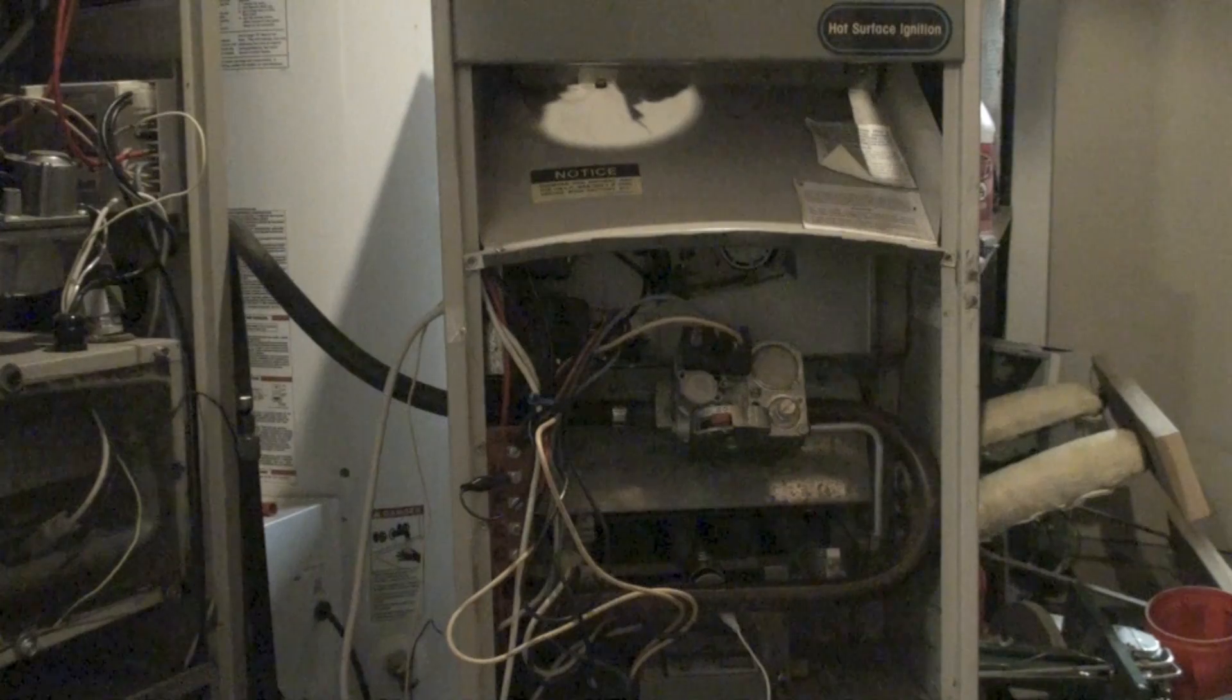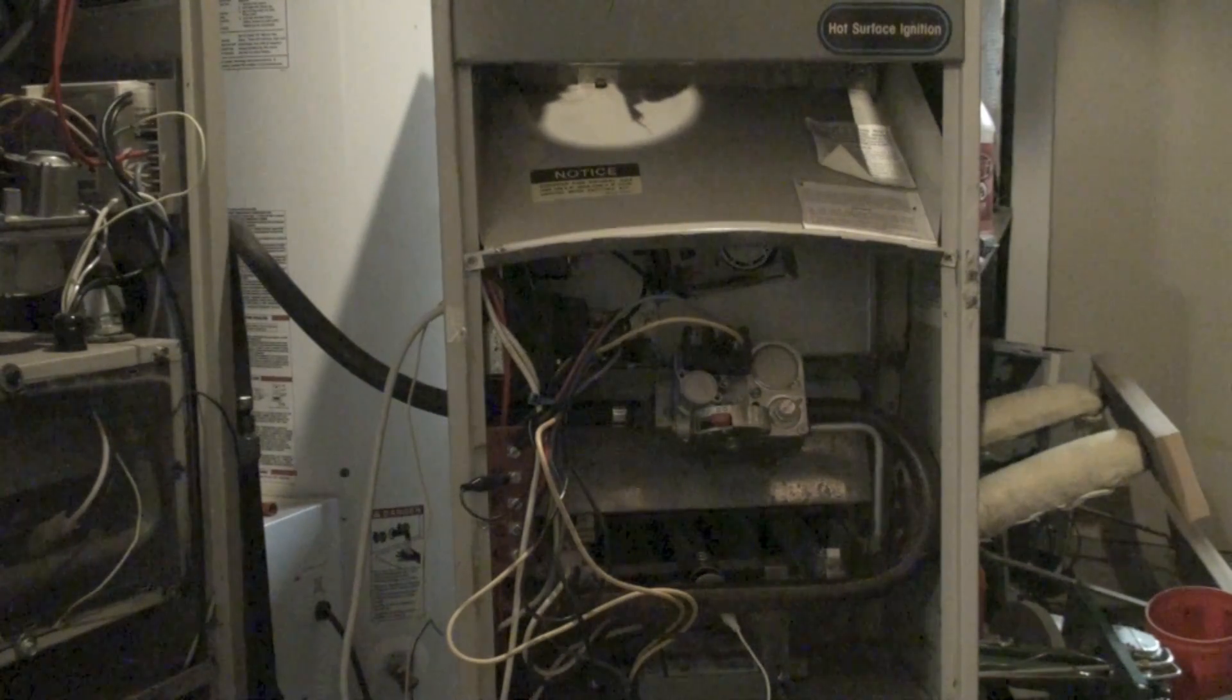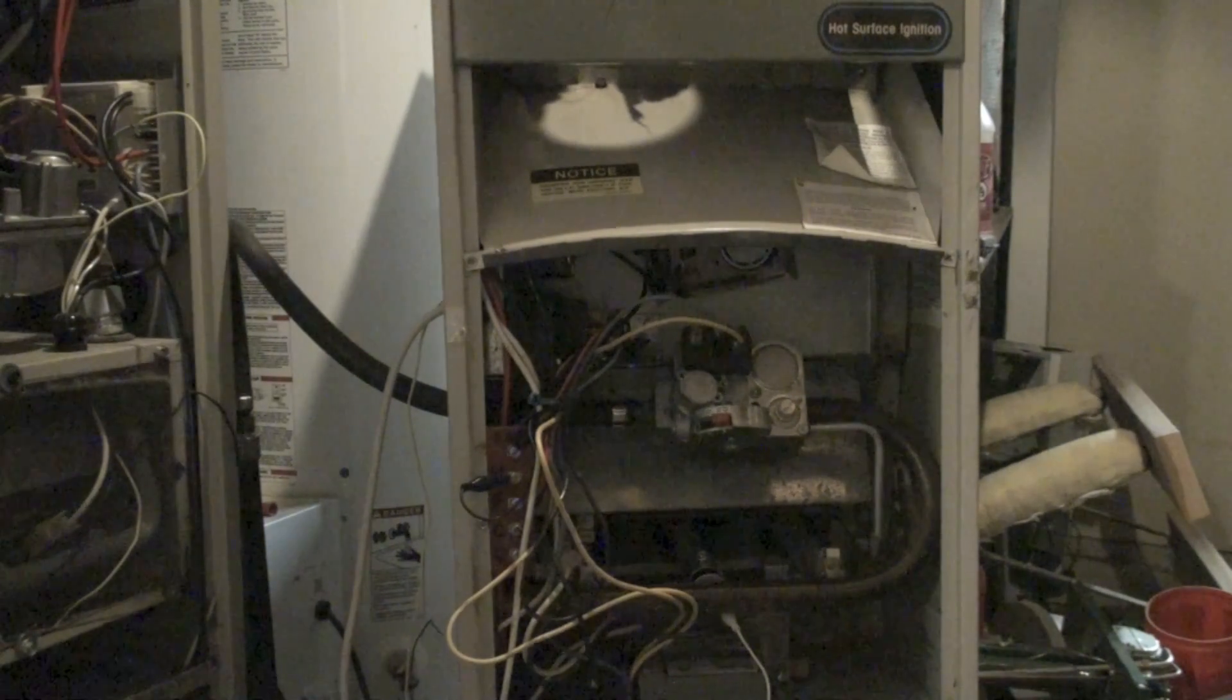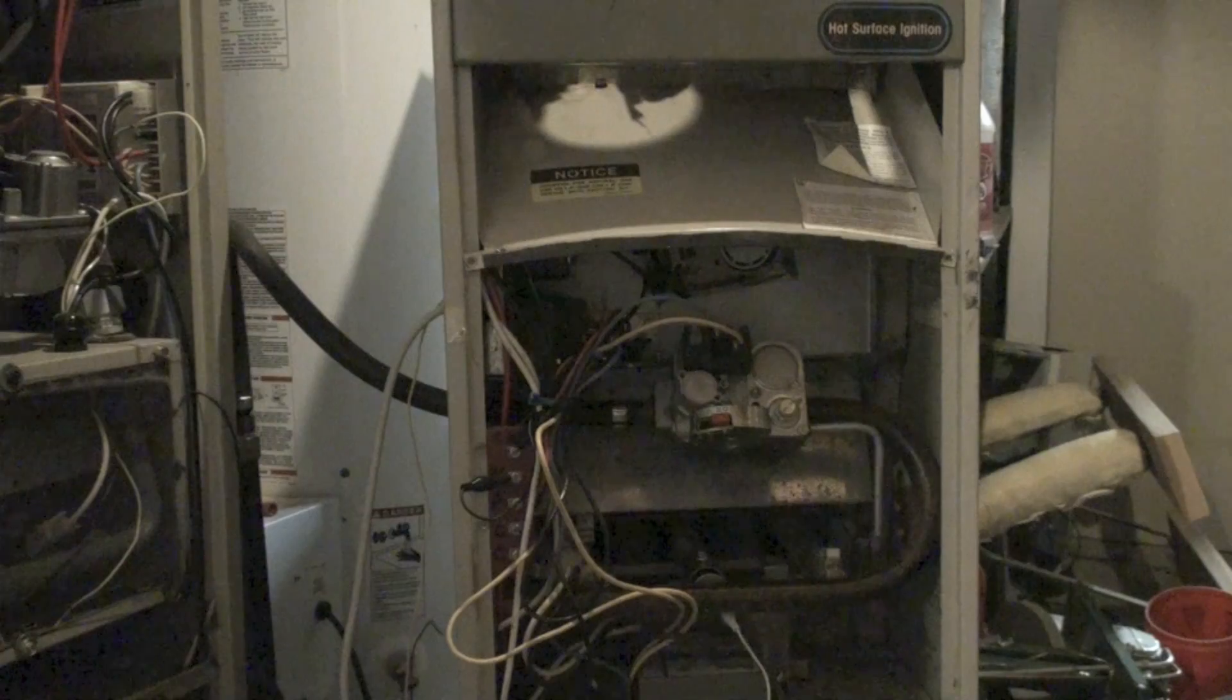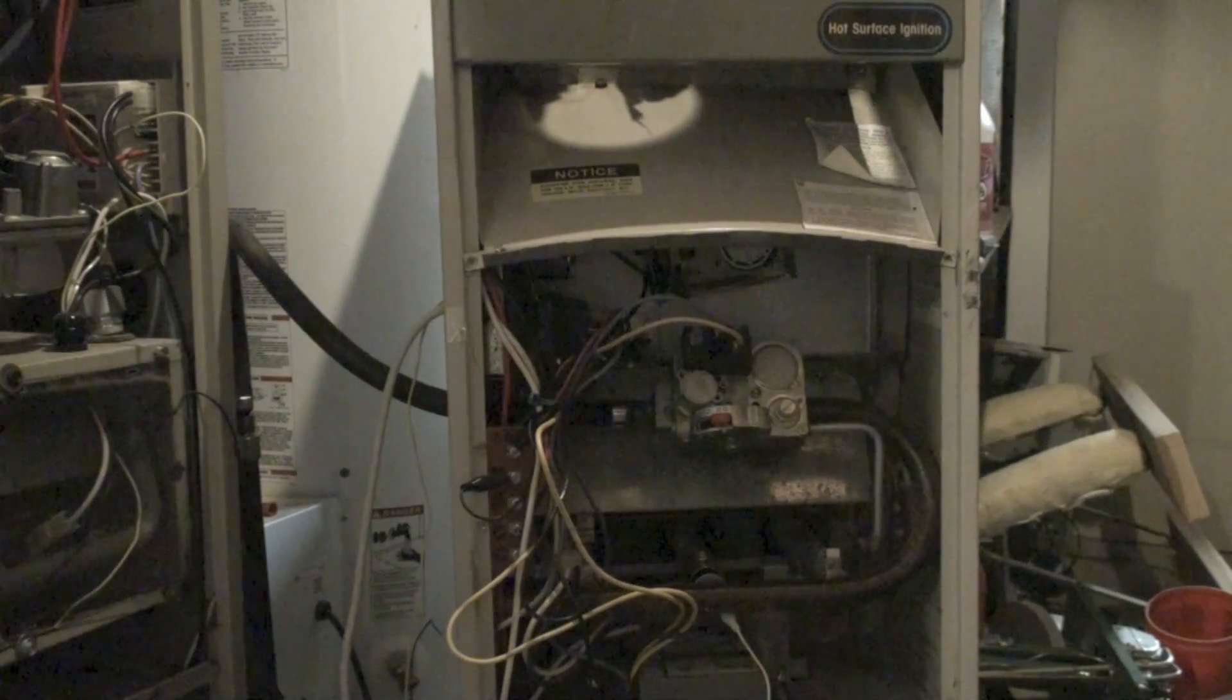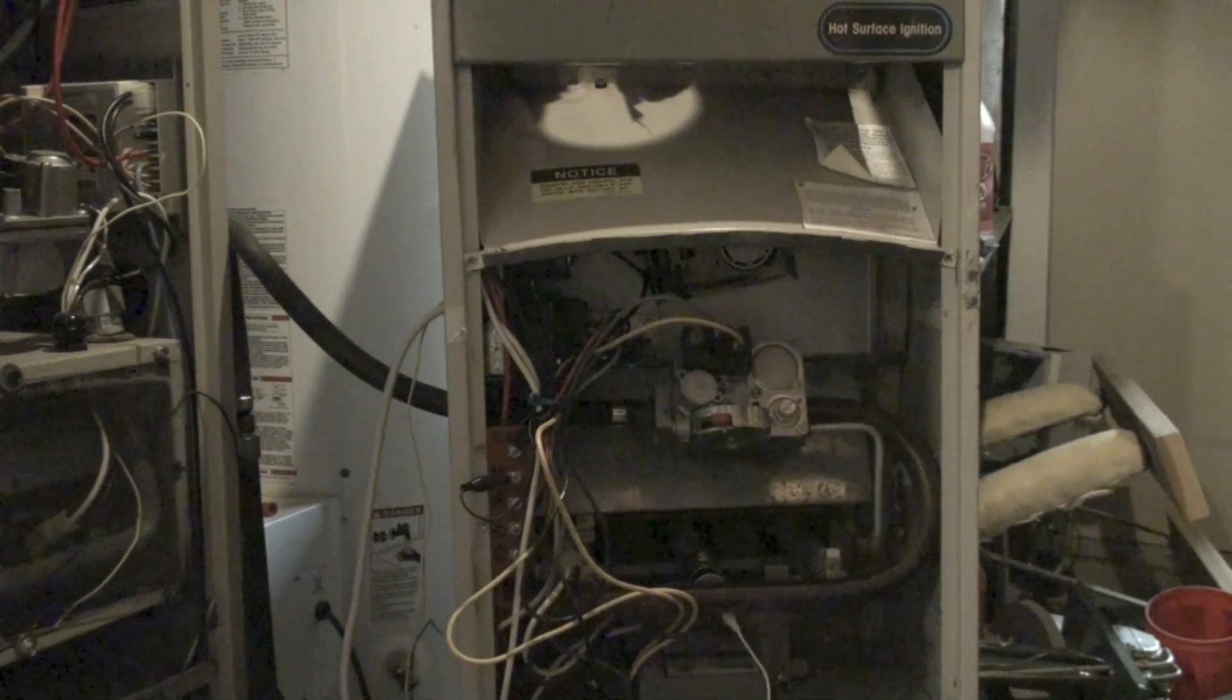It has safety shut off because it was not receiving flame sense through that hot surface igniter. Remember, the hot surface igniter is a flame sensor in this thing. It's going to try again.